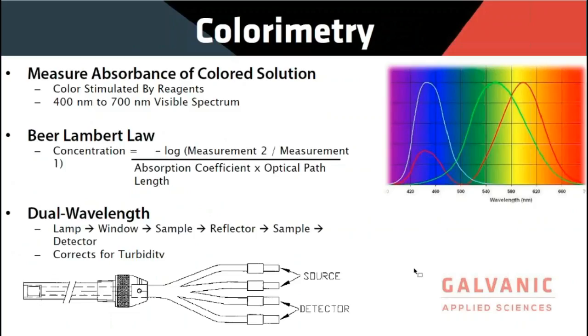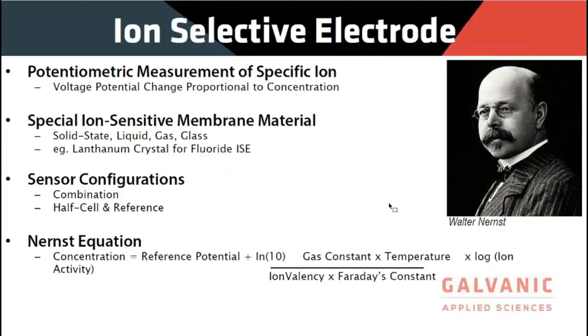So a little theory about the colorimetry. A color is stimulated by adding a reagent, and it's read in the visible spectrum from 400 to 700 nanometers. Based on the Beer-Lambert law, it's a dual wavelength measurement, so starting at the source lamp, the light travels through the window to the sample to the reflector, then back through the sample to the detector, and this is going to correct for turbidity.